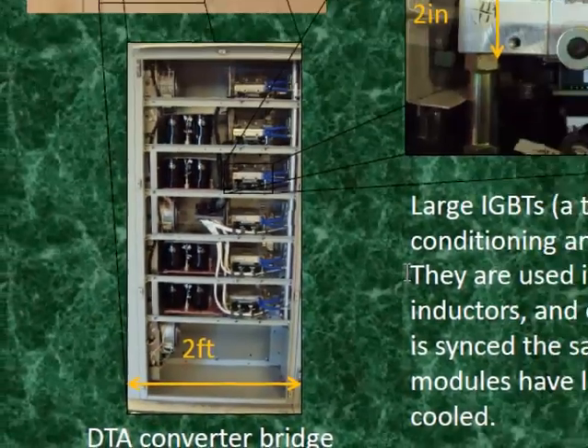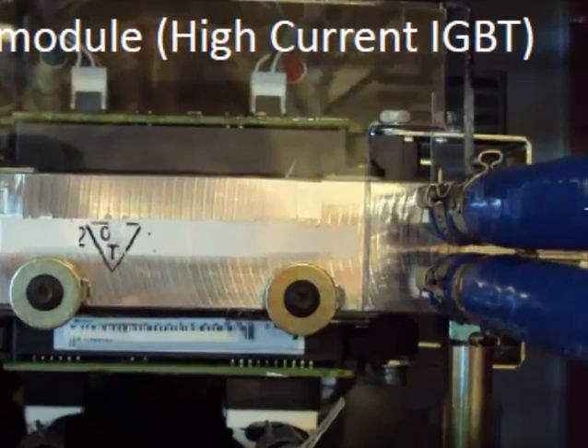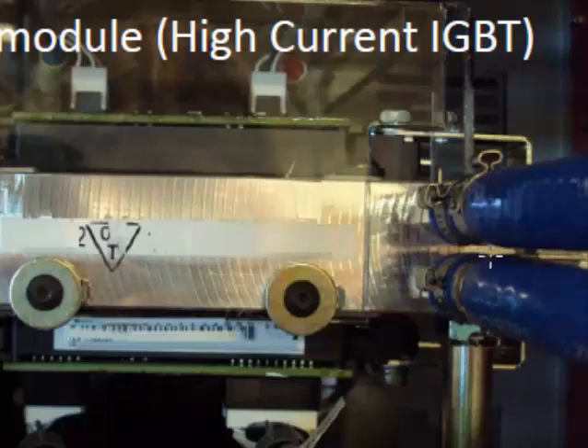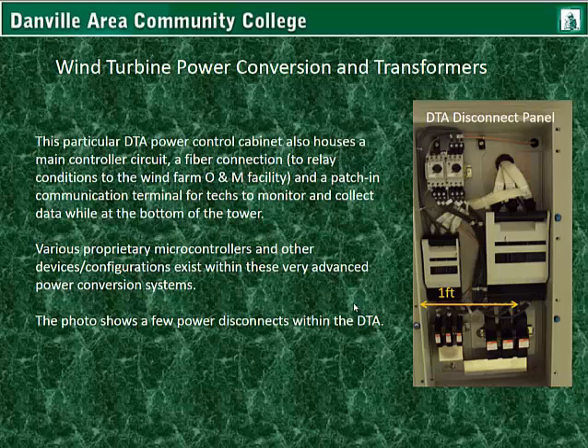This DTA is a very large cabinet. The converter bridge is used in conjunction with internal transformers, inductors, and capacitors to ensure the power produced is synced at the same frequency as the grid. The modules have losses in the form of heat and are water cooled — it's similar to a heat sink within an amplifier or a radiator in an automobile. This particular DTA power control cabinet also houses a main controller circuit, a fiber connection to relay turbine conditions to the wind farm O&M facility, and a patch-in communication terminal for techs to monitor and collect data while at the bottom of the tower.